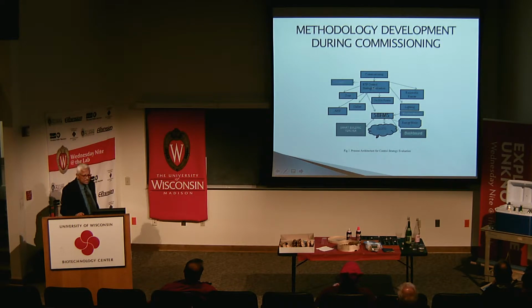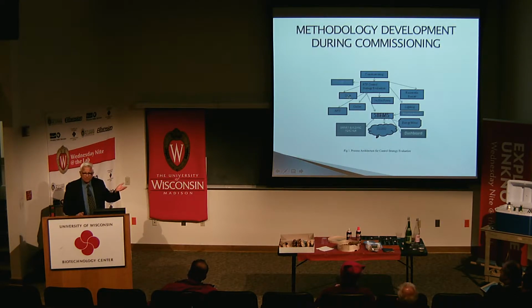Now in this phase, the customer is not aware of what the RTP pricing is going to be. He is given the RTP pricing only when he enrolls with the utility. So now during the commissioning process, the RTP pricing control strategies are evaluated for electric vehicles if you want to have power supplied back to the grid. Same thing with renewable energy. You have got zone. As I mentioned, you can raise the set point or lower the set point, as I said about optimal start and the floating control.